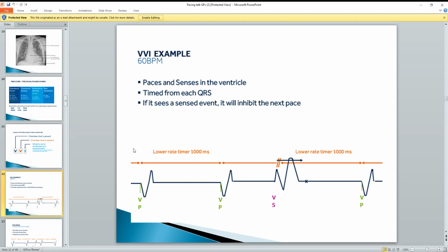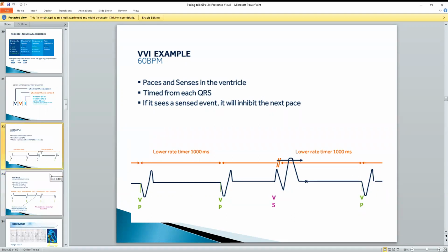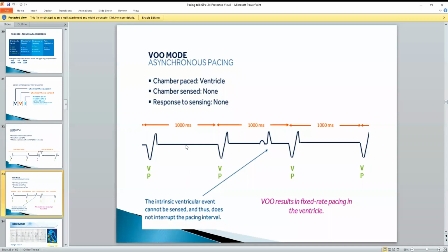So they try to encourage your own intrinsic activity. The VVI pacemaker rate is set at 60. So you can see on the diagram, you have a paced beat, and this then sets off a timer for a second. And if there's no intrinsic activity, there'll be a further paced beat. You can then see after that paced beat, there is intrinsic activity within the ventricle that's detected by the pacemaker, and this causes it to be inhibited, and it resets the timer. VOO mode is what happens when you put a magnet over a pacemaker, and that just causes it to pace at a fixed rate, regardless of the patient's own activity, which is used during surgery.